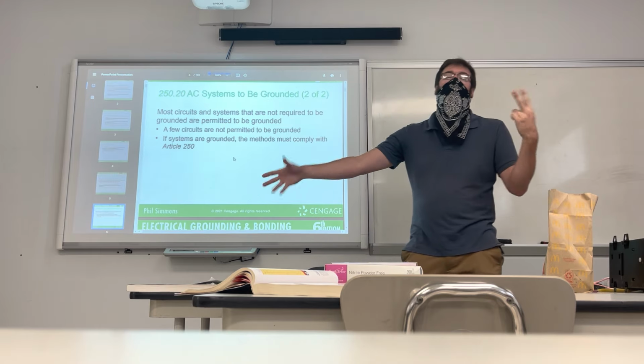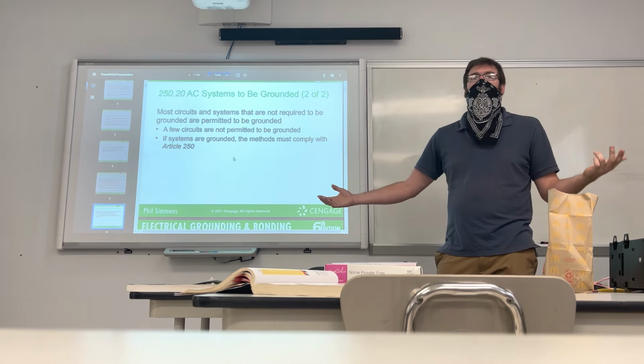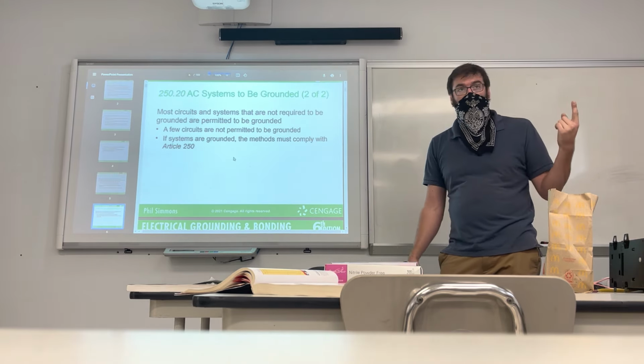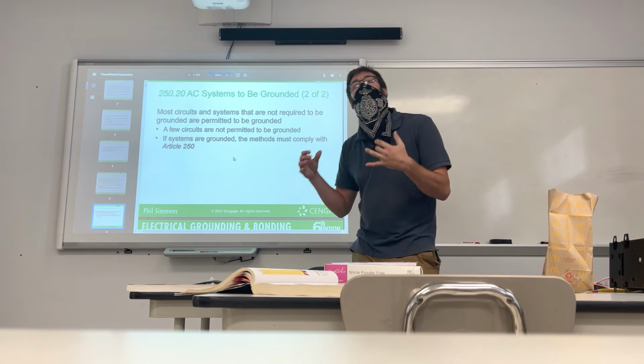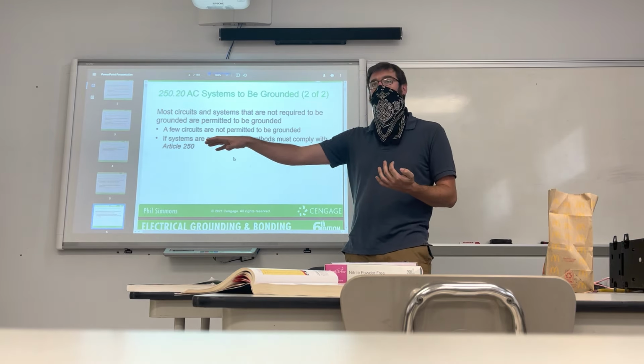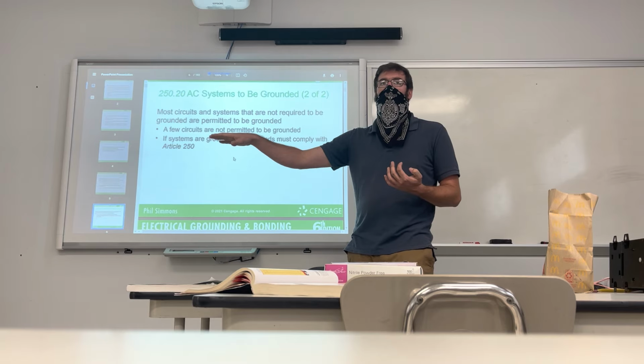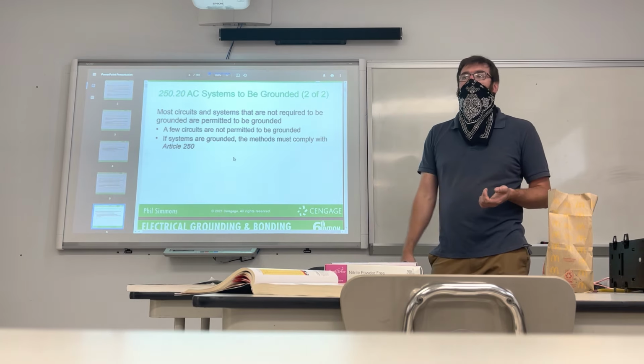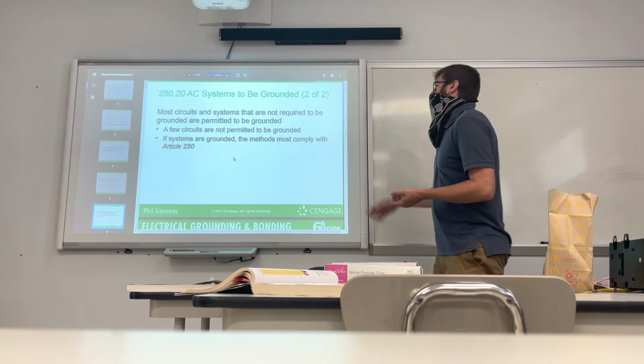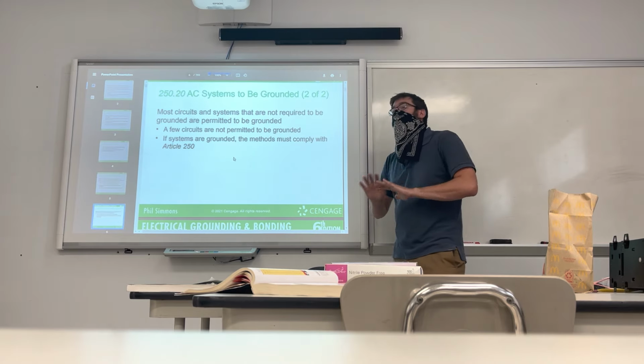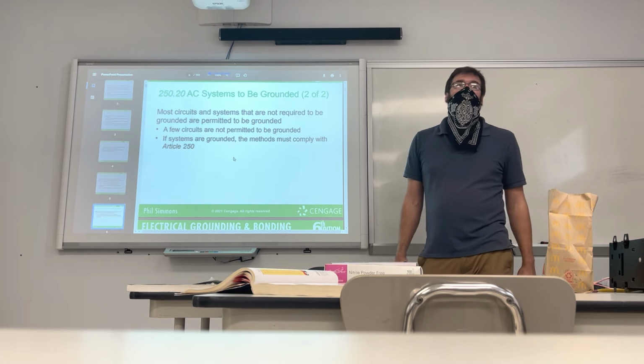If two lines were to short, yes, you're going to have a short circuit. Yes, it's going to turn off. But if that one line fails, you can have a couple electricians come and work on that while that machine is still running, still producing, and that can be rectified without even turning off the breaker. So it's one of the few systems that ungrounded is the way to go.